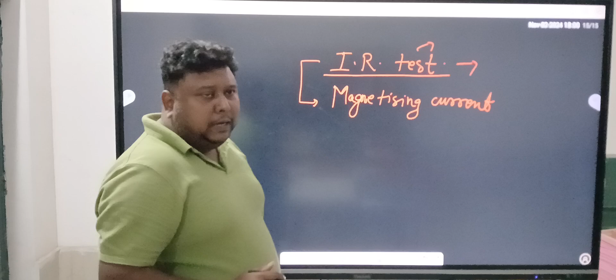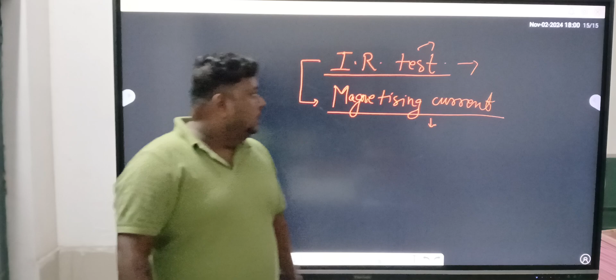Following that, the magnetizing current test. The magnetizing current test is nothing but the leakage current test. It means that if the transformer is open circuited, there is still some flow of current due to the losses and due to the induced voltage. Those currents should be in milliamperes, and should not exceed the limit. Once again, those currents should be in milliamperes. If it is exceeding, then there is some fault. So again we are going to discuss the procedural steps for this magnetizing current test.